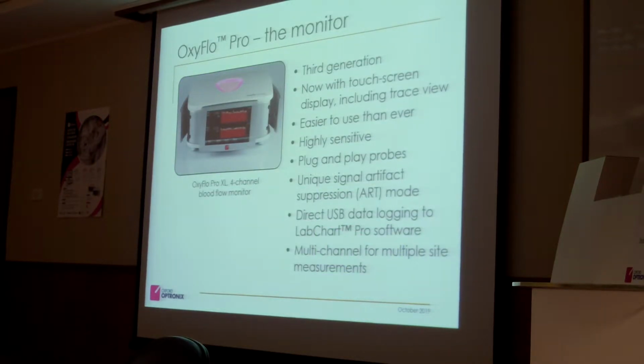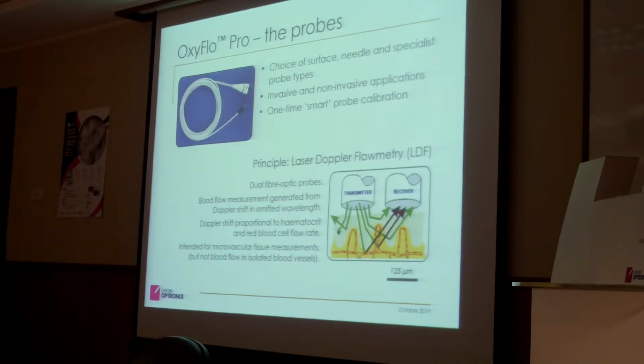The laser Doppler, I'm not talking much about that right now. If there are questions, I can answer them later. As I said, it's a standard monitor to measure microvascular blood perfusion. You have 2 glass fibers, not one like with the oxygen. So you have one where the light comes out and one where the light goes back. And depending on whether there are any moving particles, the light will be reflected with a different wavelength, which is the laser Doppler shift, and that's what we measure.